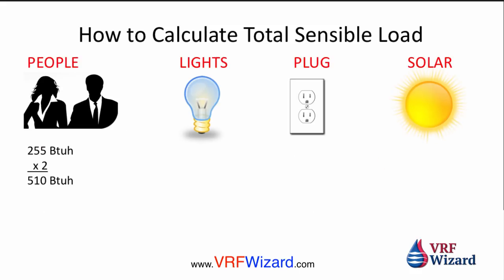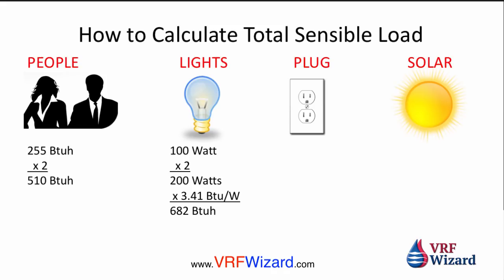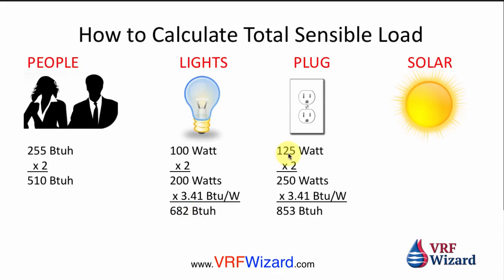Let's do a quick sample load calculation. For people, assume light activity at 255 BTUs per hour with two people — that gives a people load of 510 BTUs. This is a small office, 20 by 10 feet, so 200 square feet with two people. For lighting, two 100-watt light bulbs: 2 × 100 = 200 watts × 3.41 BTUs/watt = 682 BTUs. For plug loads, two items at 125 watts each = 250 watts.